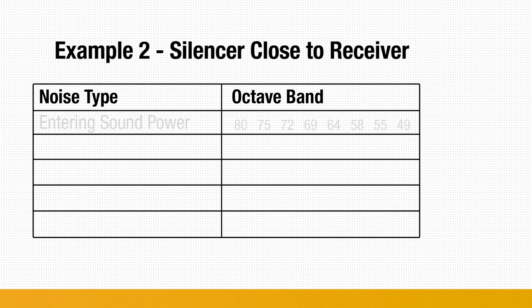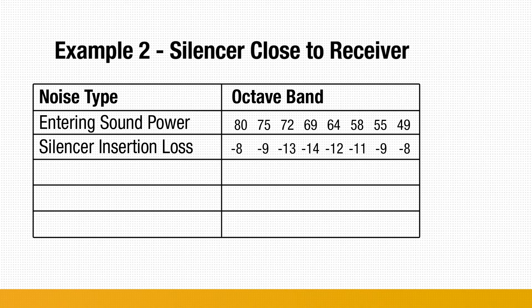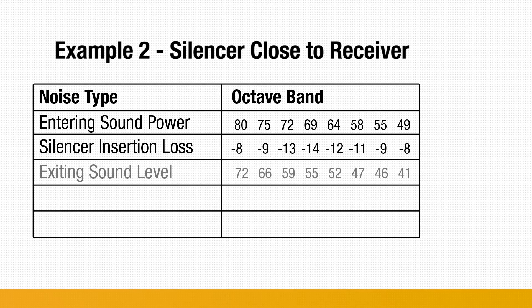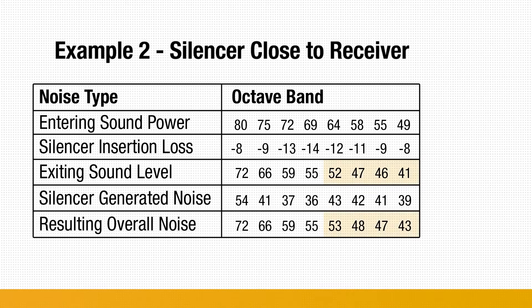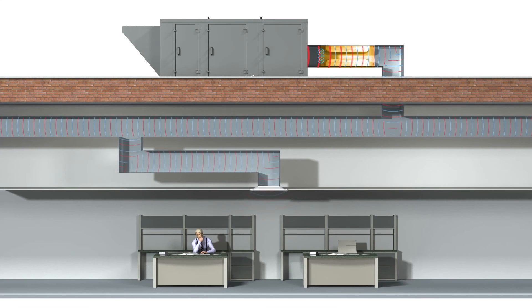In the second example, the silencer is located far from the noise source and close to the receiver. As a result, the noise levels entering the silencer are lower than in the first example. After the silencer's insertion loss is applied at each octave band, exiting overall noise levels are once again logarithmically added to the silencer's generated noise, and in some cases there is an increase in noise because both levels are within 10 dB of each other. The takeaway: locate silencers as close to the noise source as possible in order to minimize any impact from a silencer's generated noise.